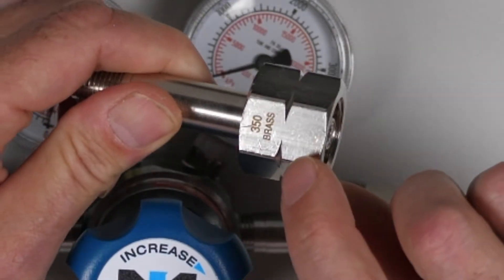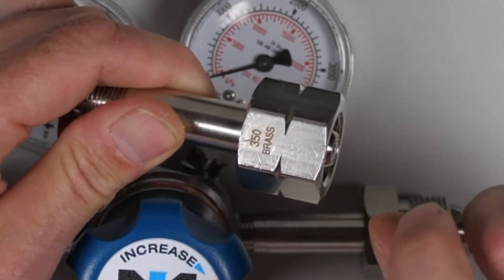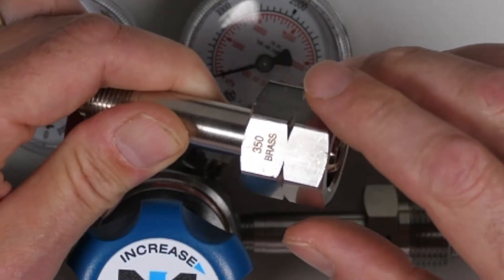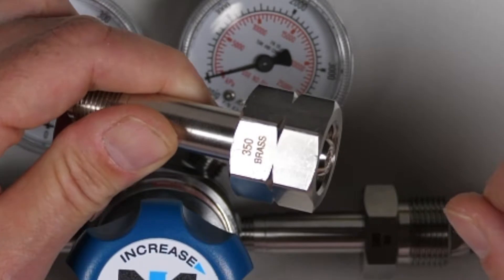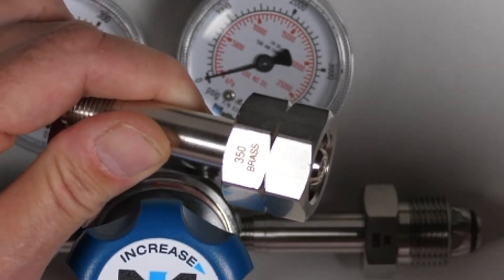The CGA 350 fitting has notches on the nut which shows that the nut has left-handed threads. CGA 350 is for flammable gases like hydrogen, methane, and carbon monoxide.